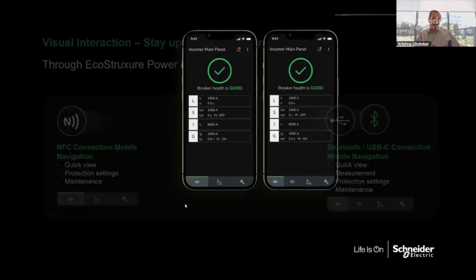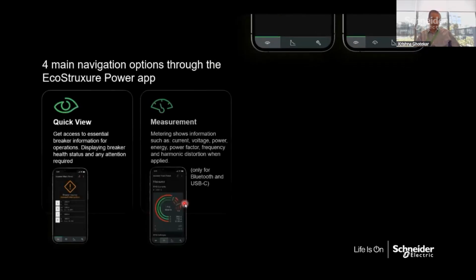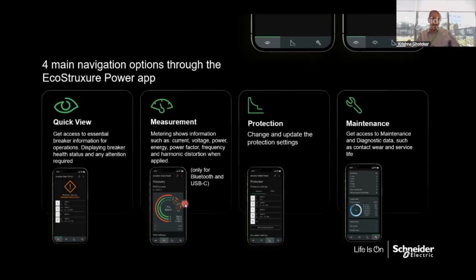And after that, you can do some settings, you can monitor the measurement parameters. If you want to download, you can download it. If you want to send it as an email to some supervisor, you can do it. If you want to add it to your cloud, you can do that. Protection settings are there. Protection settings are monitoring. If you want to change the setting, then you need an admin password. And also, if you want to limit this function, there is an option to limit the change of protection settings. Maintenance indicators you can have, like contact wear, which is now a standard feature throughout the breaker, load profile, and so on.